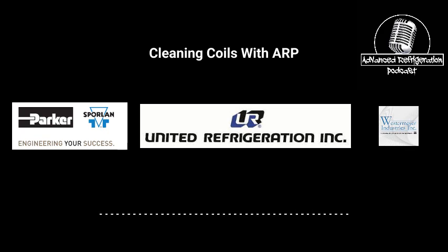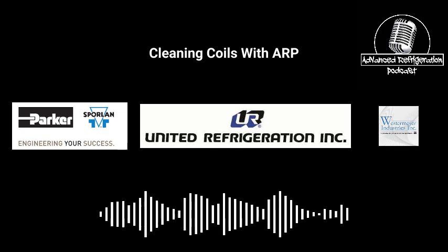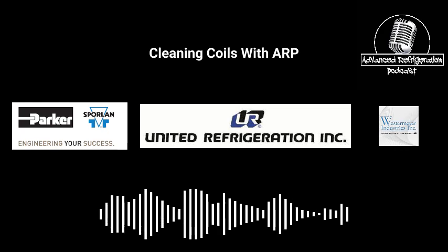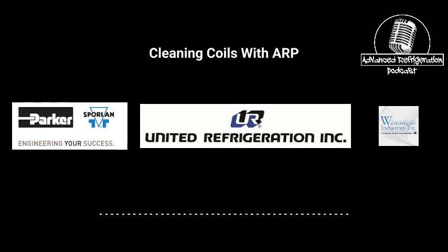So make sure that you are checking evaporator coils and honeycombs when you're working on cases. And if you're working on evaporators, this is where it gets tricky. If you have evaporators that are solid plugged up, dairy cooler coils are notorious for this because of the cardboard in there from cutting the boxes open and working in the dairy cooler. All that cardboard gets stuck to the coil.